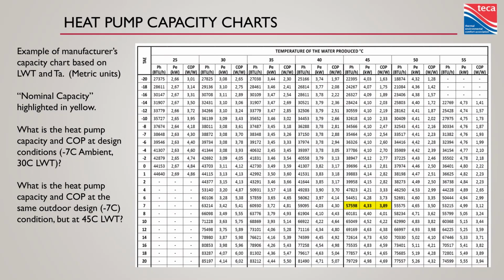Let's take a look. This is a heat pump. Actually, it's not. It's a chart. It's a fixed capacity, on-off scroll compressor monoblock heat pump. So not super advanced technology, but a good product. Happens to have a lot of data points. It happens to be rated at 57,598 BTUs when it's delivering 45 Celsius water, and it's 7 degrees outside, okay? But all these other data points around here are different than that. I've drilled that point home already.